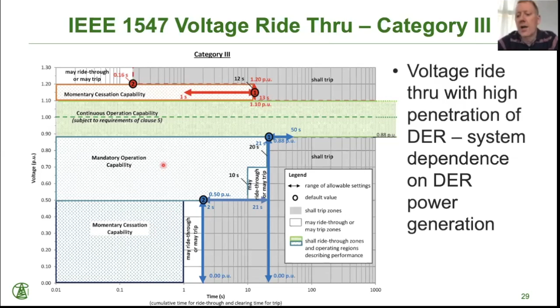This chart shows some of that ride-through behavior, where you have to be able to ride through for 1 second with no voltage at all, and ride through longer periods, like 50 seconds, even with pretty low voltage. You have to operate continuously from about 0.88 to 1.1 voltage. These are requirements built into inverters today so they're able to continuously operate and ride through.